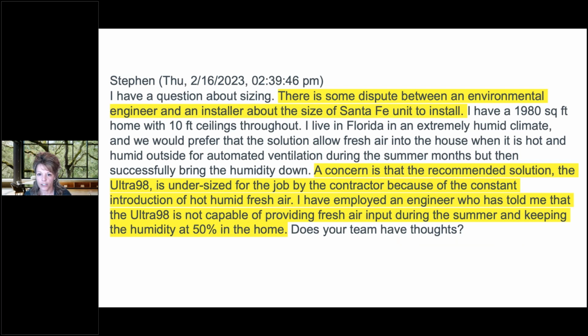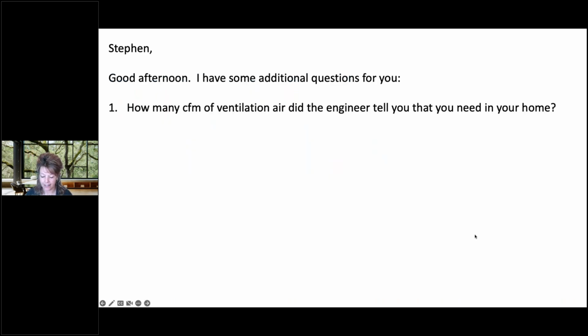So this gentleman said, I have a question about sizing. There is a dispute between the environmental engineer and an installer about the size of the Santa Fe unit. He had a 1,900 square foot house. So the engineer basically is telling him that our Ultra 98 is undersized for the job by the contractor because he wanted to use continuous ventilation of humid, fresh air. The engineer just told him that the Ultra 98 would not be capable of that. Now, we typically say up to 2,300 square feet for our Ultra 98, which is very conservative. And so ultimately, I think it should be able to handle this, but he's asking our thoughts. And so I have to go back to him and ask.